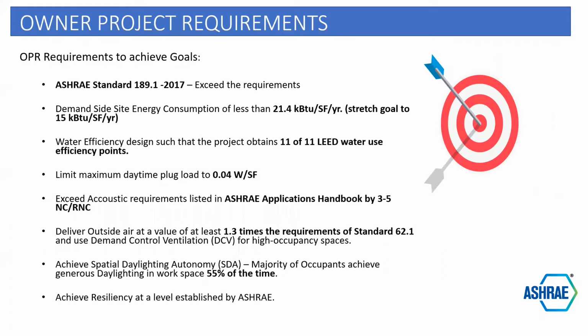And some specific OPR requirements were ASHRAE standard 189.1, to exceed the requirements of our green construction standard. Demand side energy, we wanted it to be at or less than 21.4. We hope to get to 15 kBtu per square foot per year. Water efficiency design, we need to find a way to limit daytime plug loads. As I said, acoustics. And we also wanted to be able to deliver outside air at a value of about 1.3 times the minimum requirements of standard 62.1 and use demand control ventilation for high occupancy areas.